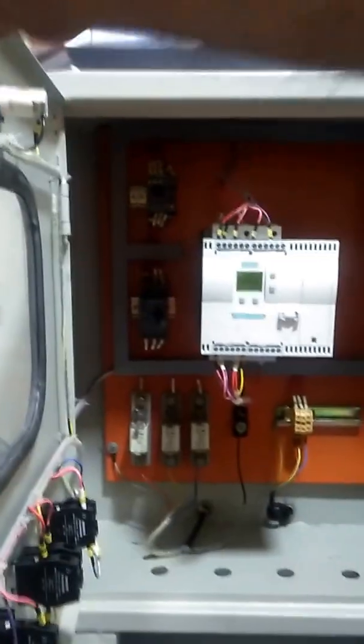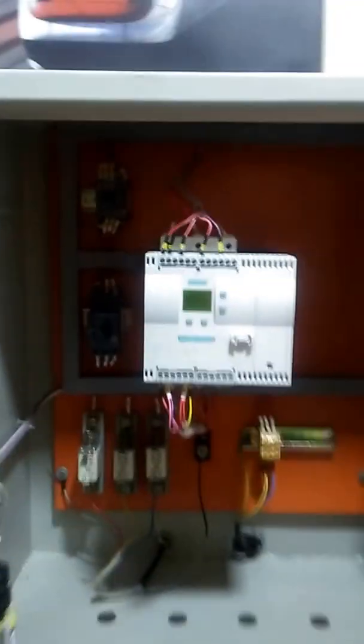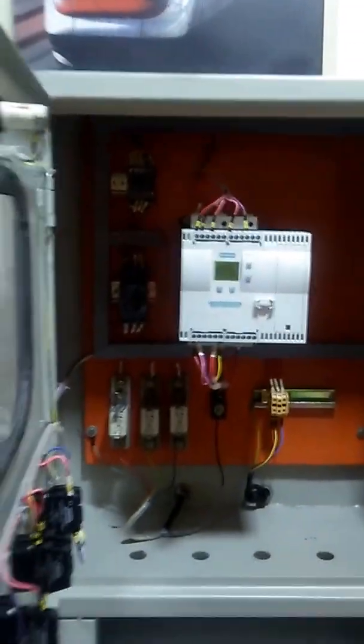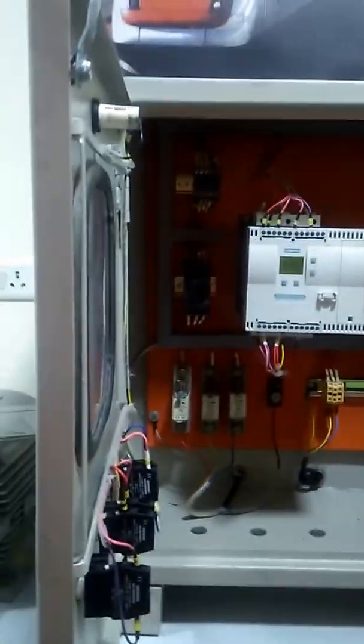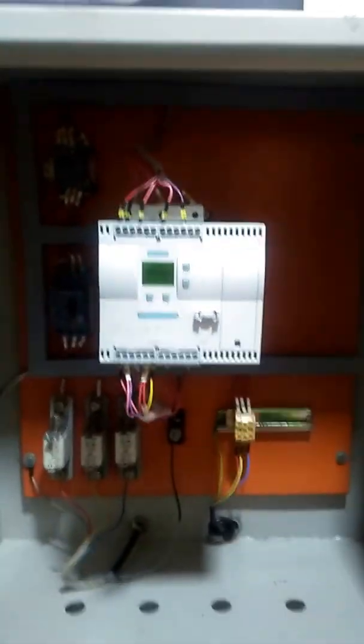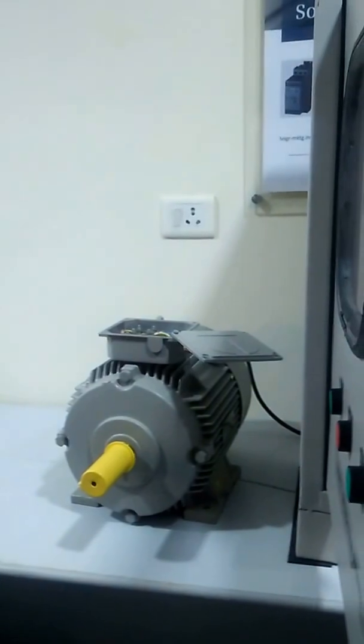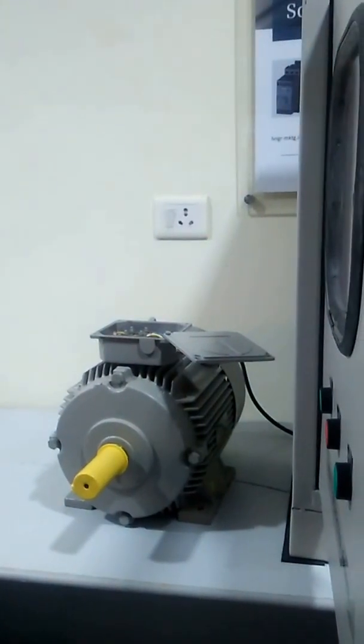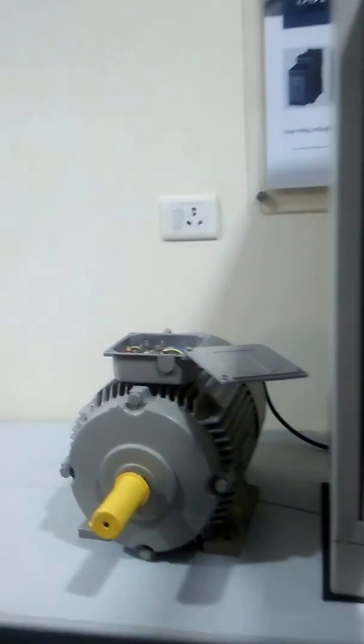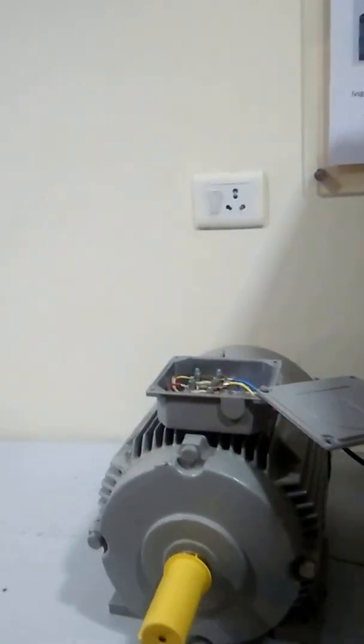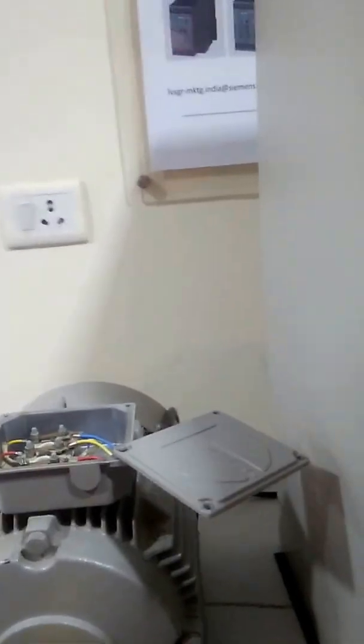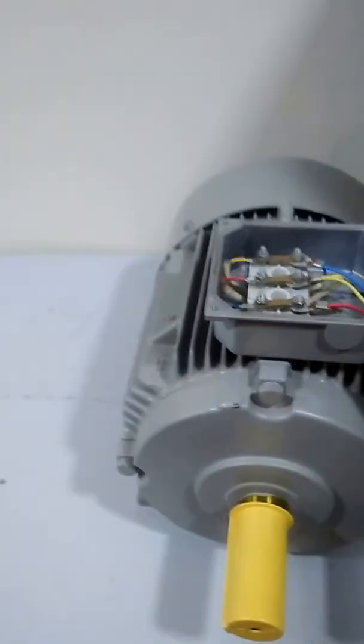Basically, the working of a soft starter is that we get the facility to set up the ramp up time and the ramp down time, which enables soft starting and soft stopping of an induction motor or asynchronous motor. It depends upon your requirement.